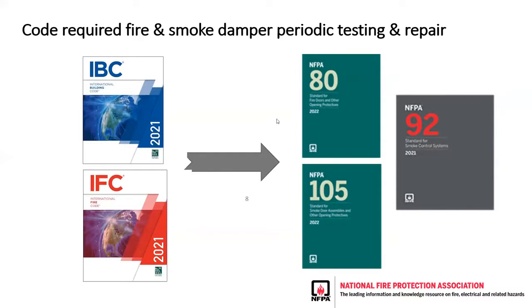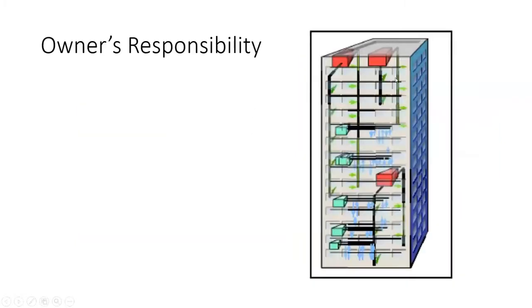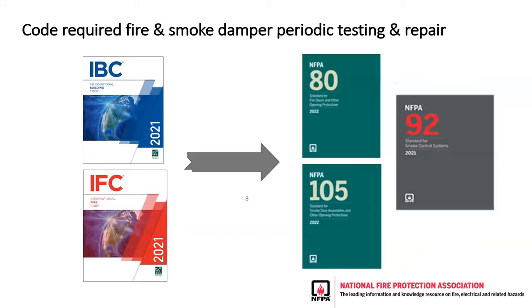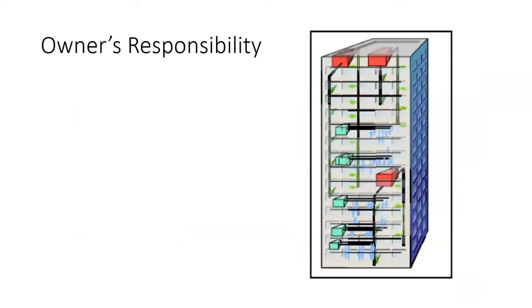So the two main codes refer to NFPA standards, 80 and 105. They aren't long. 80 is fire, 105 is smoke. The sections aren't long, but they clearly require testing and repair of a damper. You can replace it if it's not in good condition. Blade clash, you're never going to get the blade straightened out in the field. So in a case like that, you'd have to change the damper. It's rare. Next. So to rub it in, it's the owner's responsibility to take care of this and not the fire department or building officials. Next.